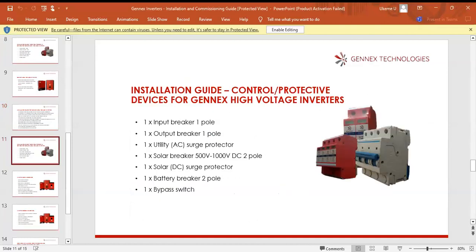Installation guide: the control and protective devices for Gennex high voltage inverters include the list below. One input breaker, one output breaker. These are single pole, not double pole. You are advised to use single pole. Neutral normally should go direct to a common terminal. Don't use double pole, to make the installation simple and trouble-free.